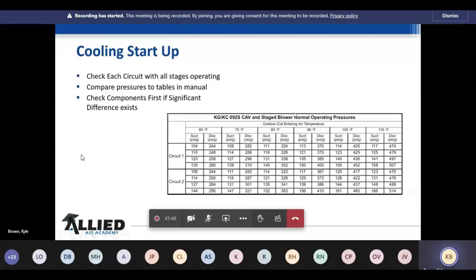And then on the cooling startup, you'll see these are constant air volumes. So on the cooling startup, these pressures, circuit 1, circuit 2, do remember that these are checked in a lab situation. So if you've got a kitchen where everything's hot down there and you did a replacement unit, especially an emergency replacement, your pressures are going to be a little bit different than what this chart is. You always want to get these things 24 good hours of running, letting them get into a steady state. Even when you adjust a charge, you need to wait 15 minutes before you even consider the numbers that you're seeing anyway. You want that expansion valve to get settled in, let it start metering and throttling correctly.